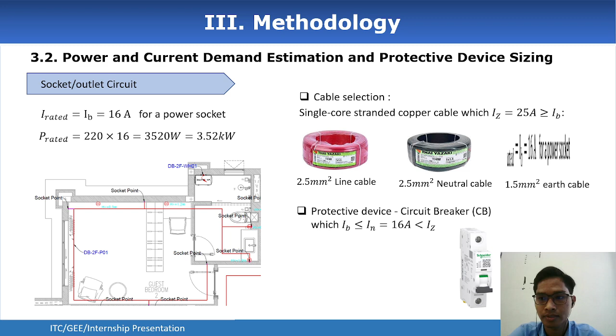We choose the cable which has current carrying capacity greater than the design current. So we choose the 2.5 square millimeter cable which has current carrying capacity IZ equal 25 amps. And for the protective device, we choose the circuit breaker which has nominal rating current 16 amps. We choose this circuit breaker so that the nominal rating current IN is between the design current IB and the current carrying capacity of the cable IZ.